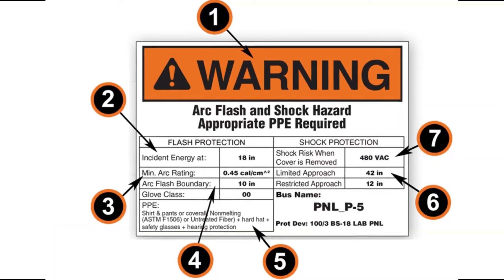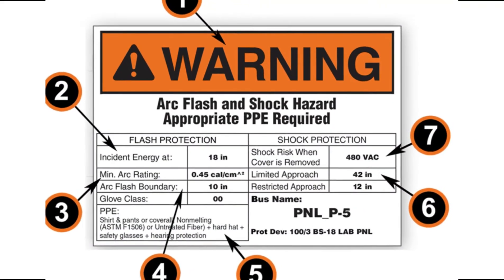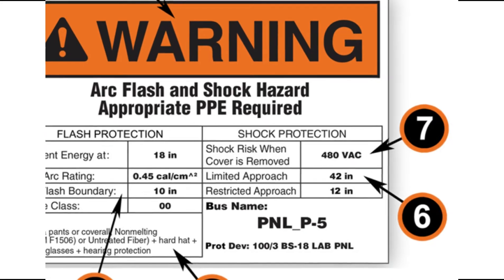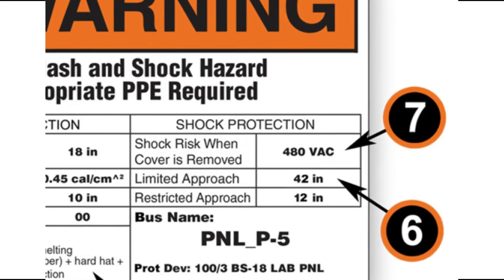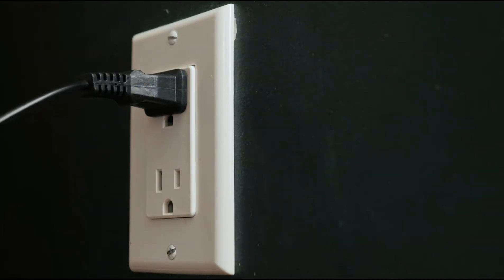Number six: limited approach and restricted approach fields — these are shock hazard approach boundaries, defined in more detail in the arc flash workplace safety guideline. The prohibited approach boundary was also removed in the 2015 NFPA 70E edition. Number seven: shock risk when the cover is removed. The nominal voltage of the equipment must also be listed on the label. The nominal voltage of a circuit or system is a nominal value assigned to the circuit for the purpose of conveniently designating its voltage class. For example, the nominal rural residential voltage in the U.S. is 120 volts, although the actual voltage may range from 114 to 126 volts.